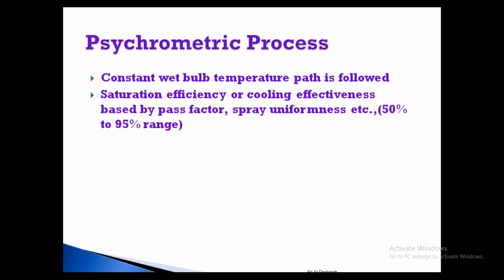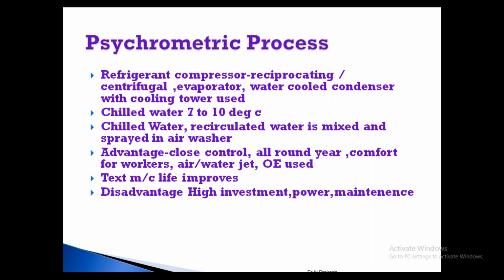Uniform spray, the amount of water you spray, evenness, and the velocity of the air going into the chamber all matter. Then you can attain the higher RH. As Ashok sir was explaining, even though you achieve the best RH after the air washer, distribution losses are there. First of all, you have to create this maximum RH. Our motto is to create the best efficiency, so I will explain all those things.